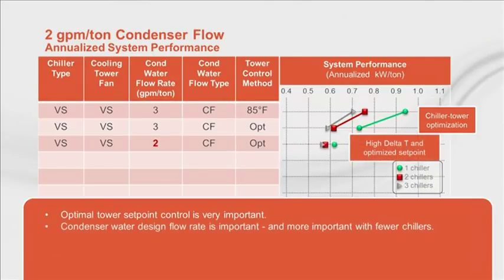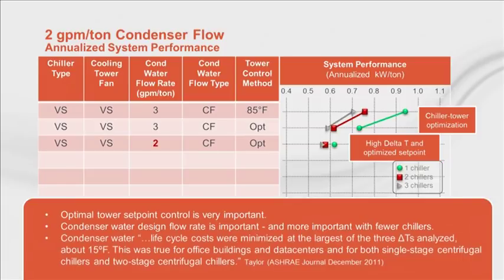The lower flow rate provides very good savings for fewer chillers, but as the number of chillers increases, the performance benefits are less significant. This lines up with the industry's understanding of flow rates and is true for all chiller manufacturers. Taylor described the same results in an article published in the December 2011 ASHRAE Journal. In that analysis, he reduced pipe sizes, which also reduced some of the possible condenser water pump energy savings. So his lowest life cycle cost was derived from a combination of lower first costs and lower operating costs.